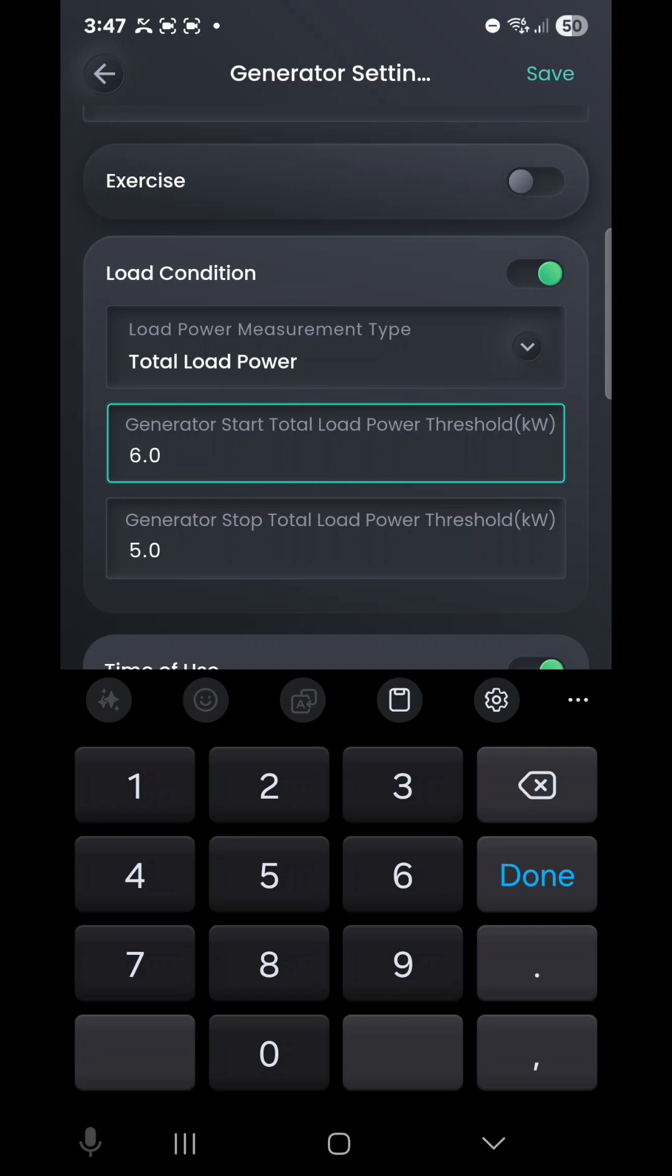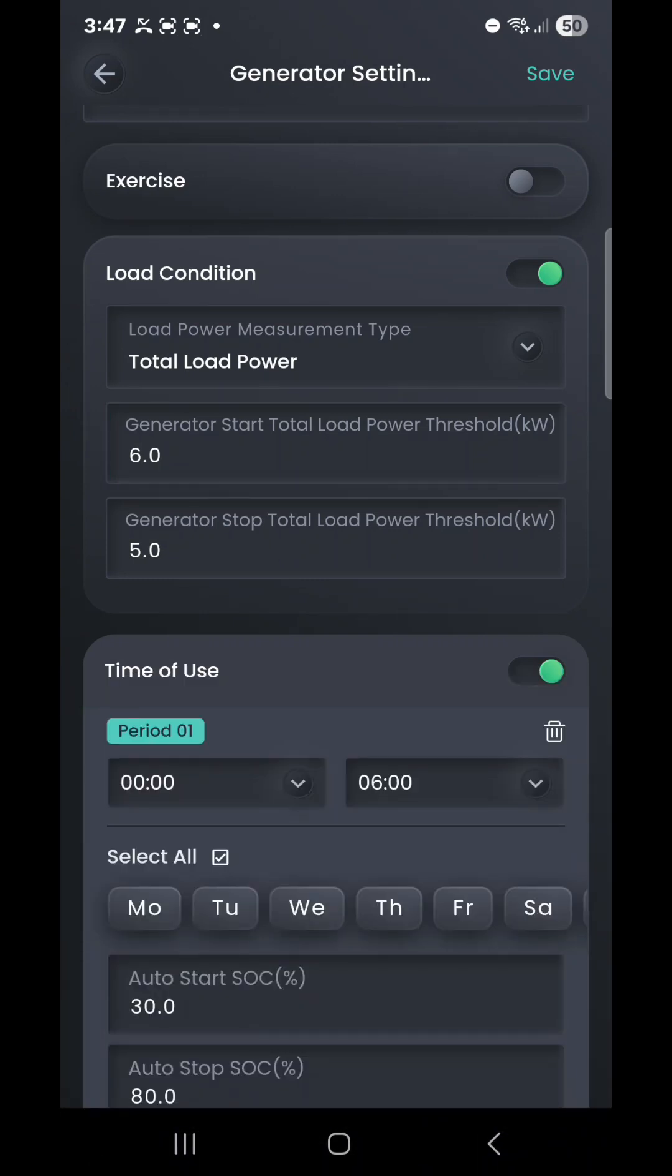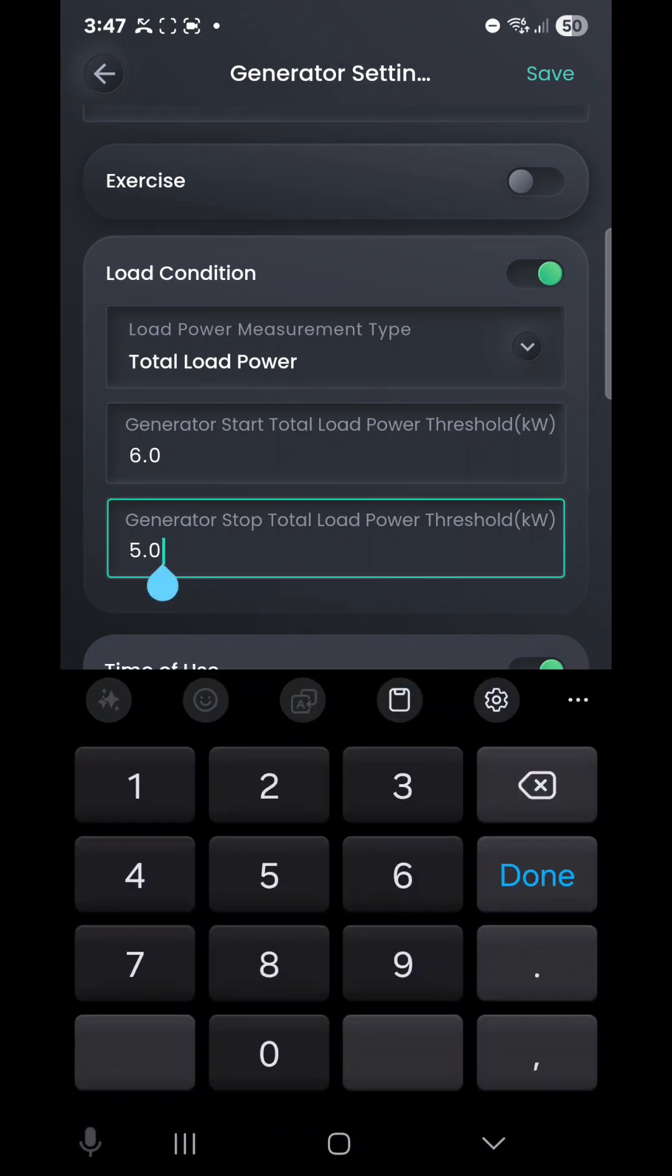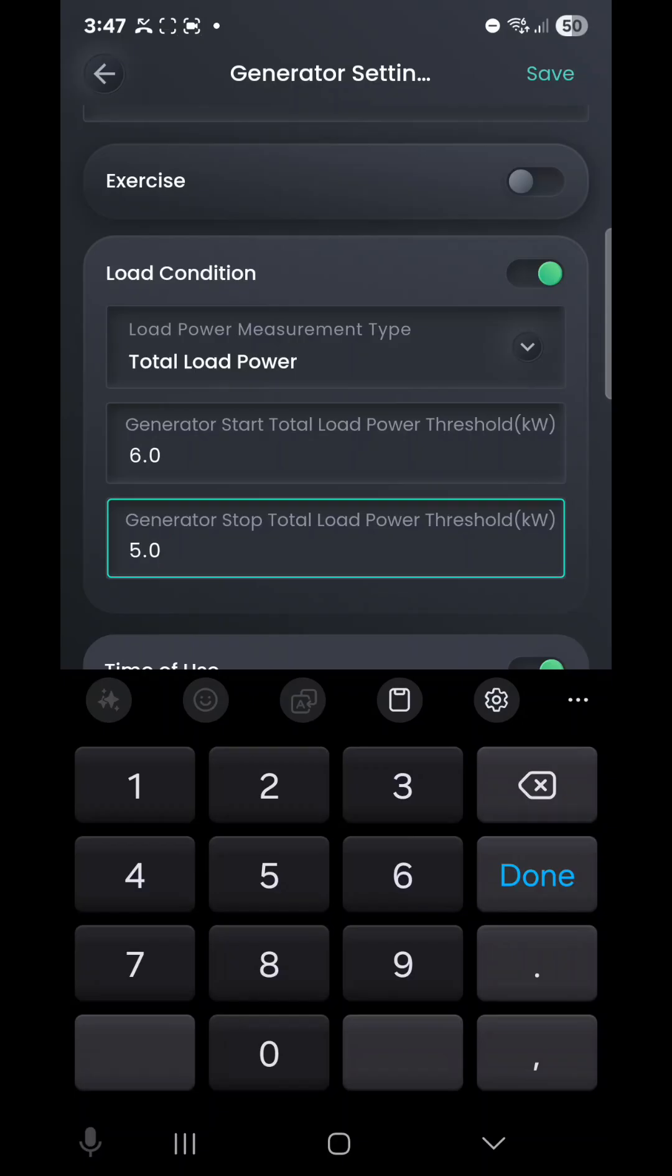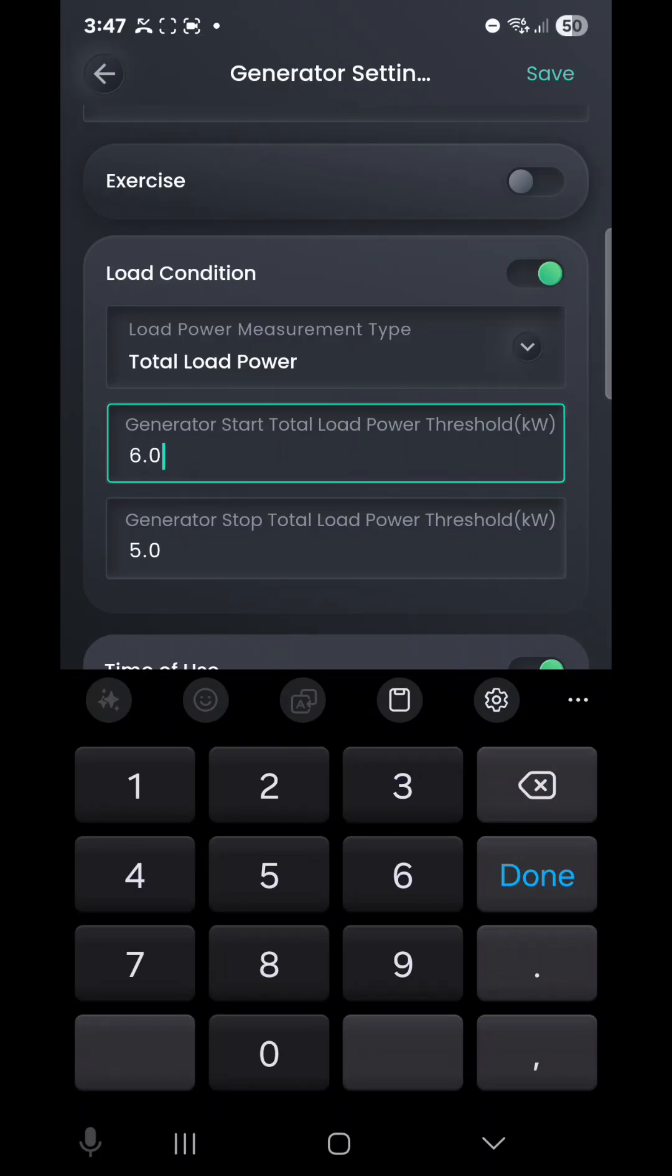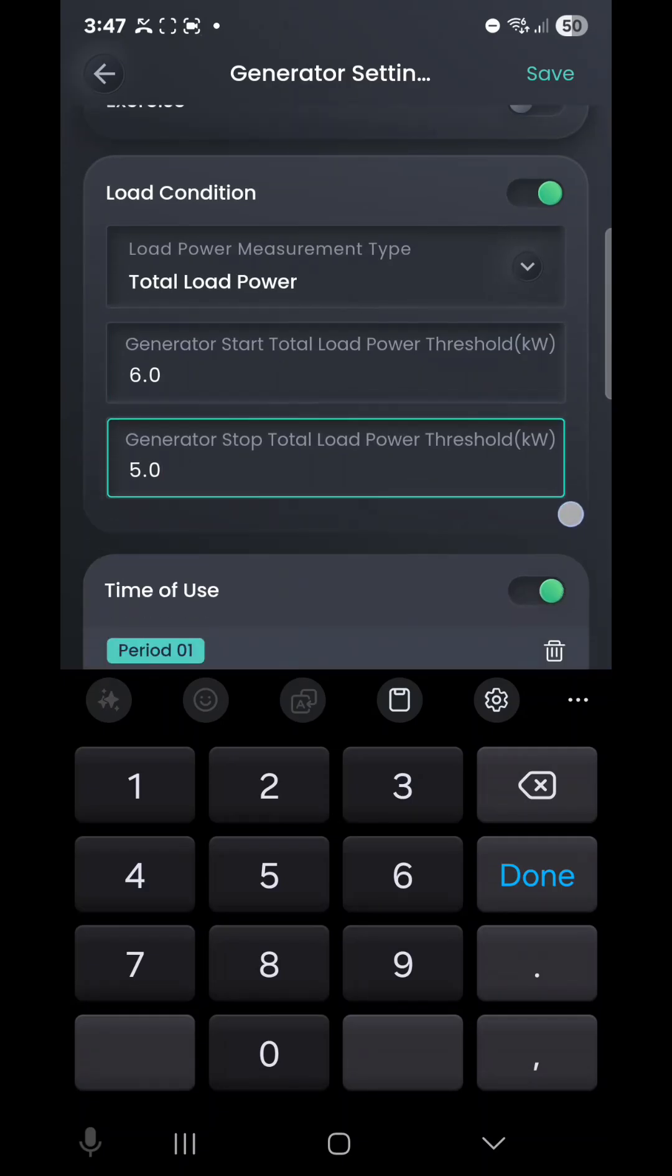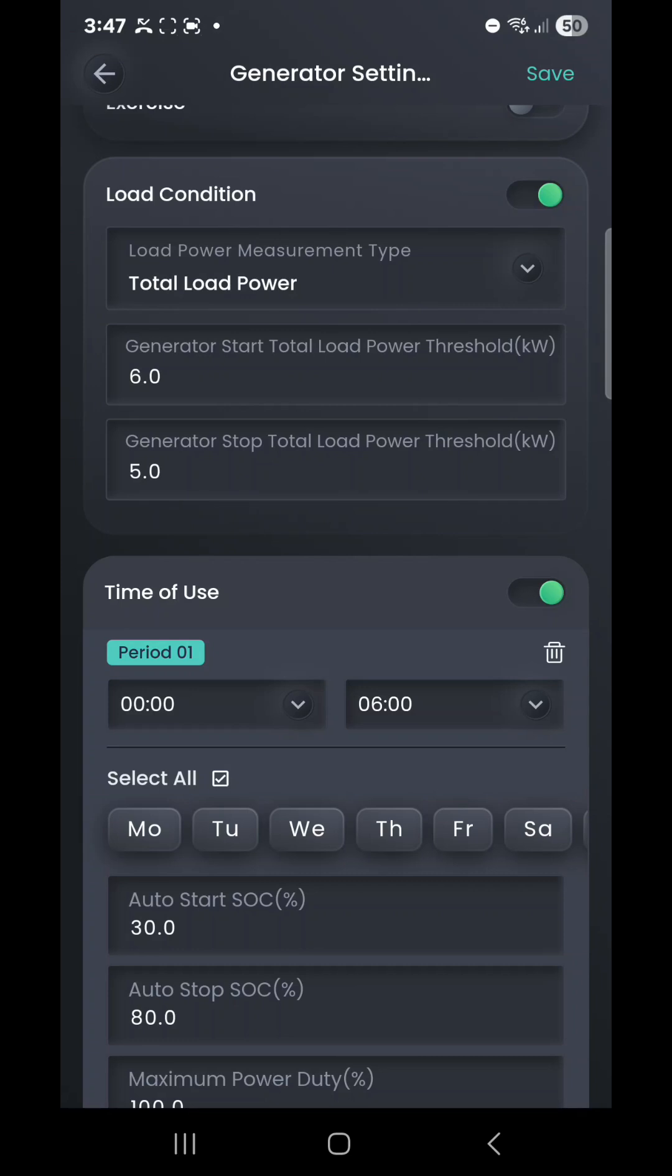Once you've finished using those power-hungry devices, your power consumption will drop, and we generally set this generator stop total load power threshold to a kilowatt under the inverter rating. So, once again, six-kilowatt inverter, a five-kilowatt shutoff point. If you've got a ten-kilowatt inverter, then your start load total power will be ten kilowatts, and your shutoff will be nine. That's essentially how you configure it. Just keep in mind it's going to be based on the inverter capacity you've got on that particular site.